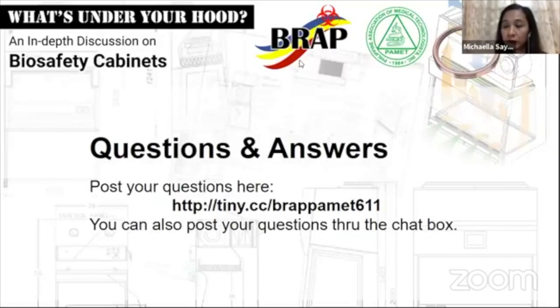I failed to mention the size of the biosafety cabinets. There are actually several sizes. I think there's a 3 foot one, there's a 4 foot, 6 foot, and there's the longer 8 foot version. Now, again, you need to determine first what you would want to do. Basically, if you have a 4 foot biosafety cabinet, you cannot fit 2 persons.